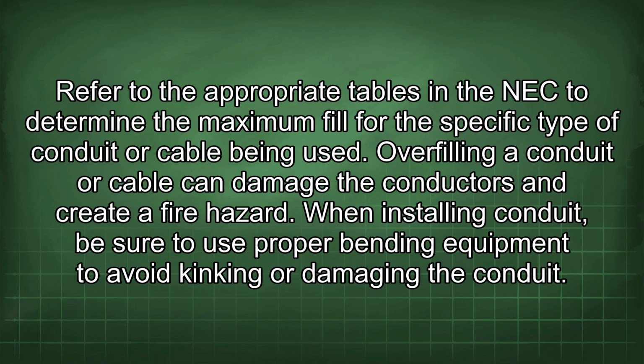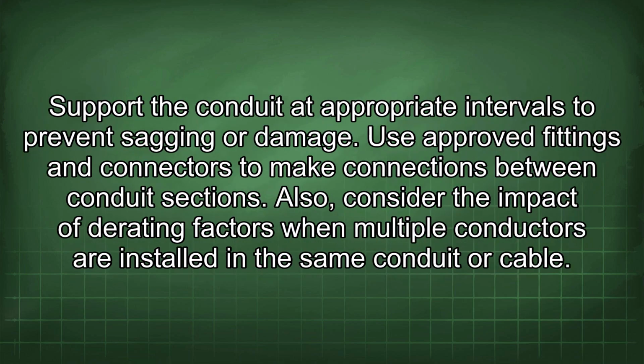When installing conduit, be sure to use proper bending equipment to avoid kinking or damaging the conduit. Support the conduit at appropriate intervals to prevent sagging or damage. Use approved fittings and connectors to make connections between conduit sections.